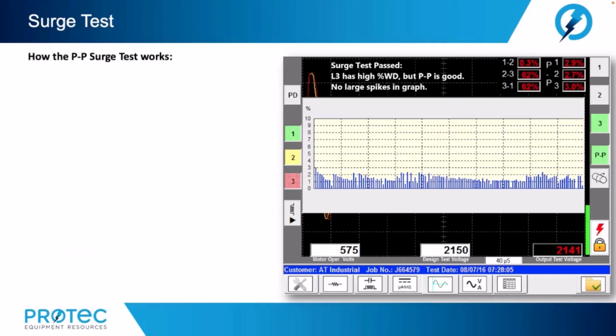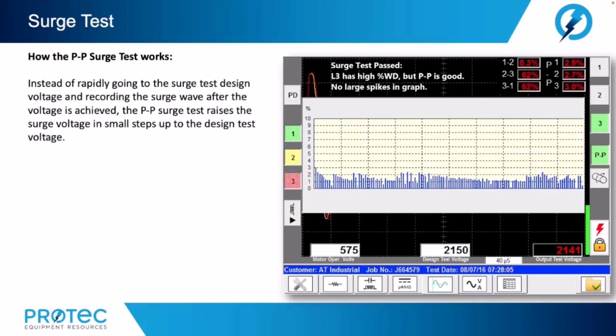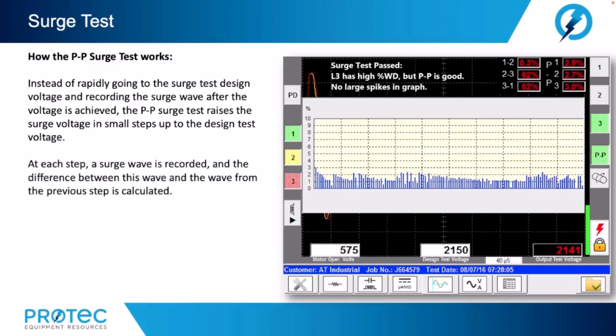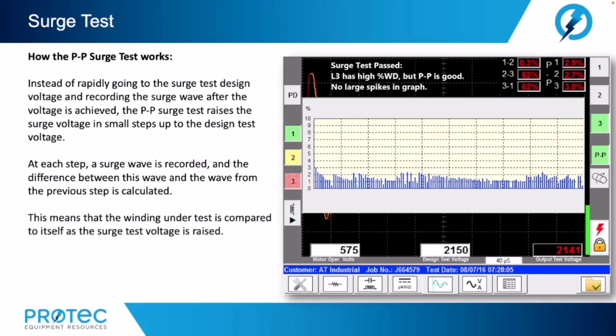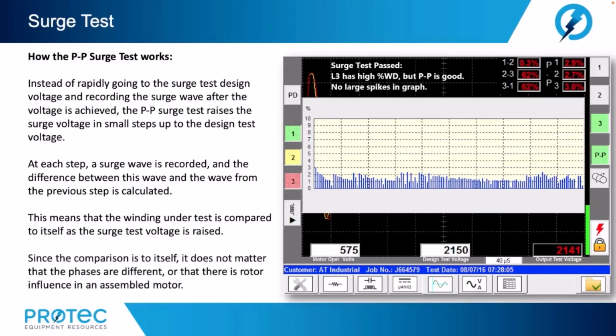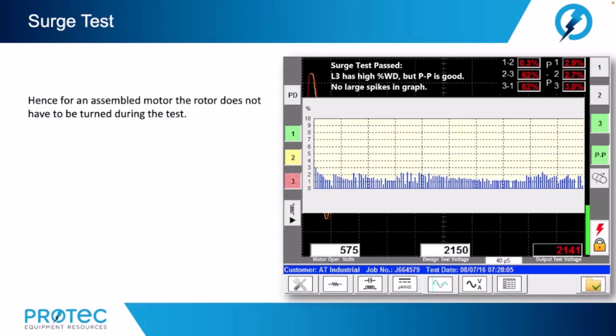Now, how the P2P surge test works. Instead of rapidly going to the surge test design voltage and recording the surge wave after the voltage is achieved, the P2P surge test raises the surge voltage in small steps up to the design test voltage. At each step, a surge wave is recorded, and the difference between this wave and the wave from the previous step is calculated. This means that the winding under test is compared to itself as the surge test voltage is raised. Since the comparison is to itself, it does not matter that the phases are different or that there is a rotor influence in an assembled motor. Hence, for an assembled motor, the rotor does not have to be turned during the test.